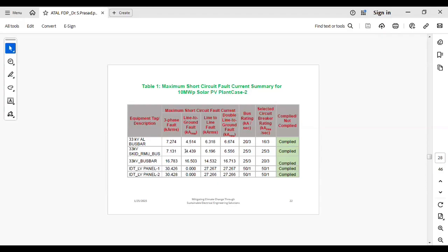Based upon this, you will decide what the breaker rating should be, or whether the short circuiting withstand capacity of the bus bar is exceeding the short circuiting current level, or it is within limits. If the short circuiting current is exceeding, then you have to use a different rating of bus bar to withstand it, because if a short circuit happens, that much current will be injected. So you have to have components that withstand that current. Therefore, we are conducting this test and verifying. Finally, we provide a report that it is complied.